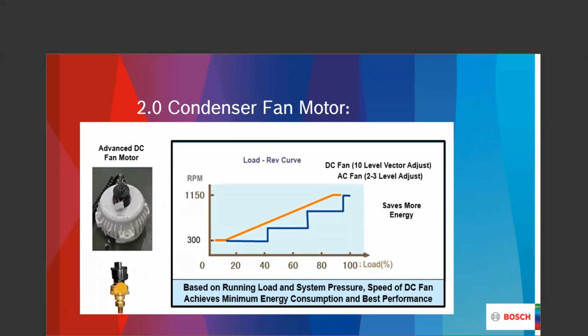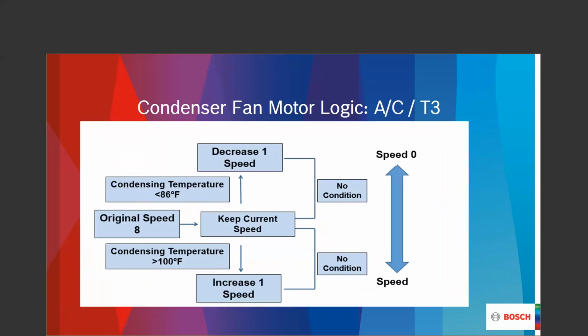So what we're looking at here is we're going to get that particular temperature from the refrigerant pressure. Remember that pressure is temperature. And we're looking at whether we need to go down in speed. If my liquid line temperature gets below 86 degrees, we're going to go down in speed. If that temperature gets above 100 degrees, then we're going to go up in speed. If it stays the same temperature-wise between the 86 and the 100, we will keep the current fan speed.